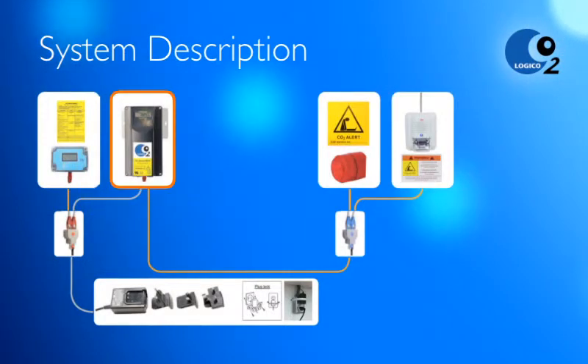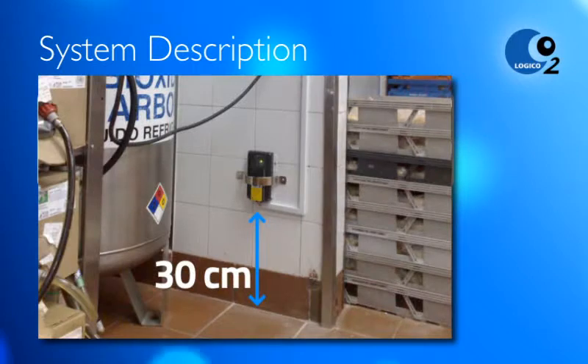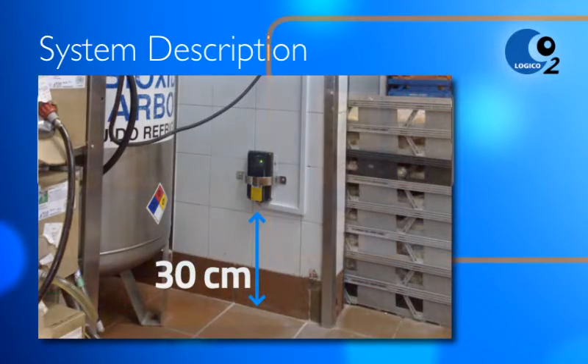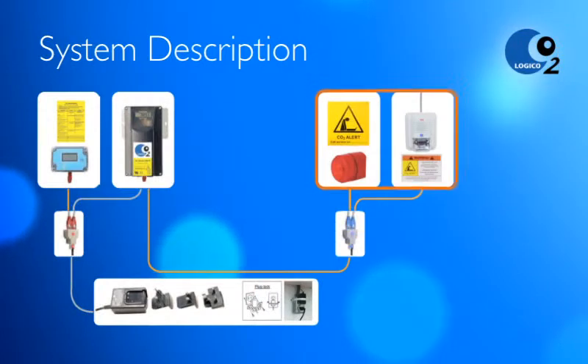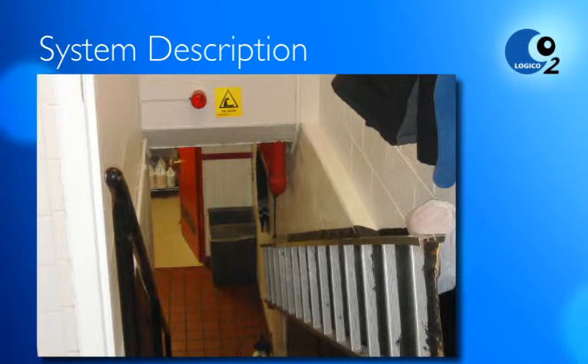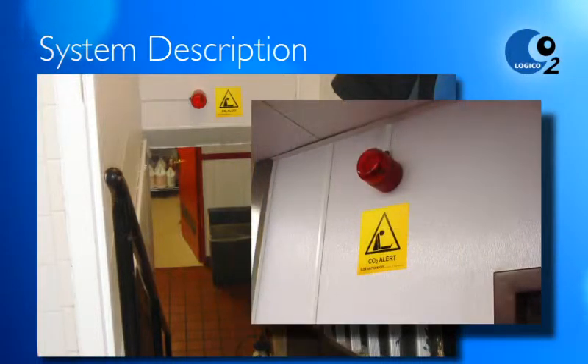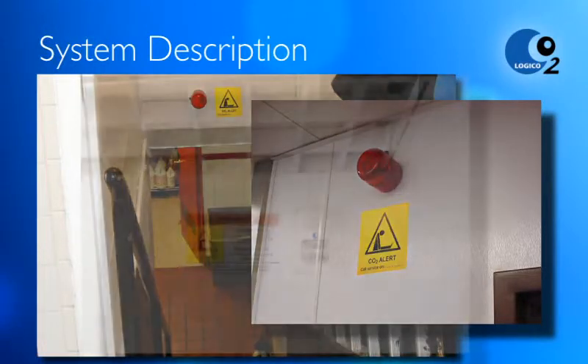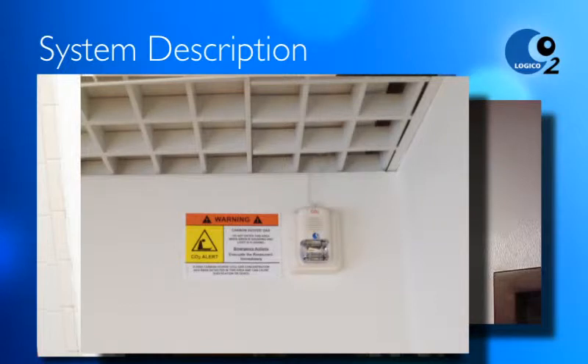The CO2 sensor should be mounted in the vicinity of the CO2 tank, or if you have a basement, in the basement. When you have a basement store, the warning lamp will be mounted before you enter the basement. In stores without a basement, the warning lamp will be mounted so that the crew can easily see it. The white horn strobe should be mounted in the danger zone and is an indication to evacuate the area immediately.